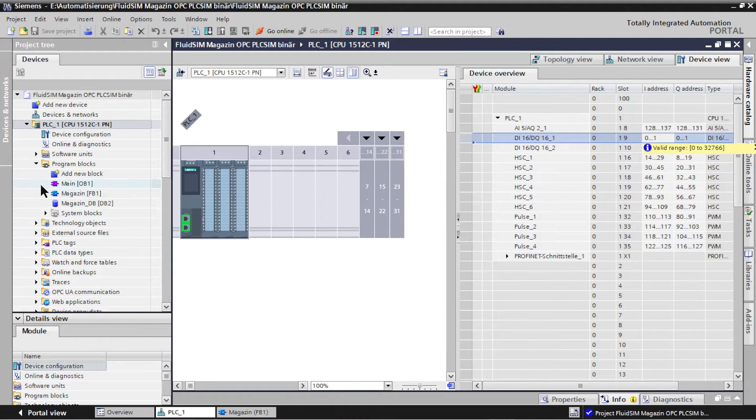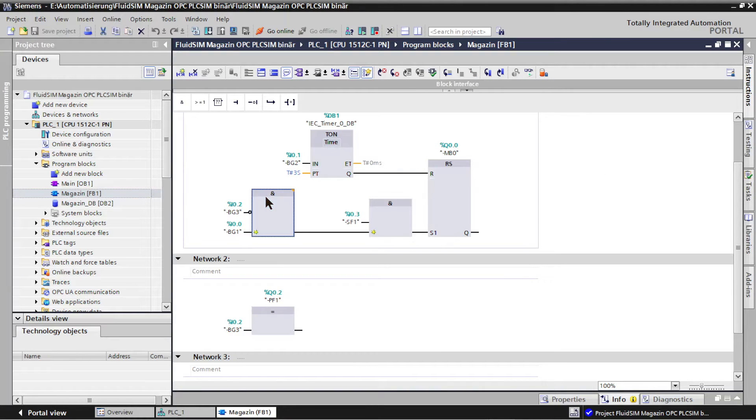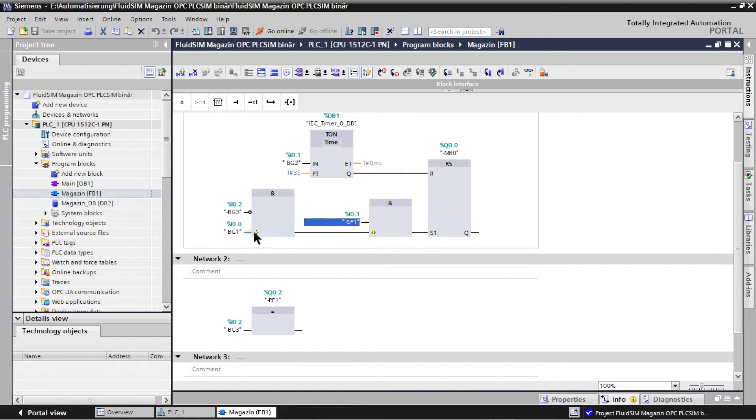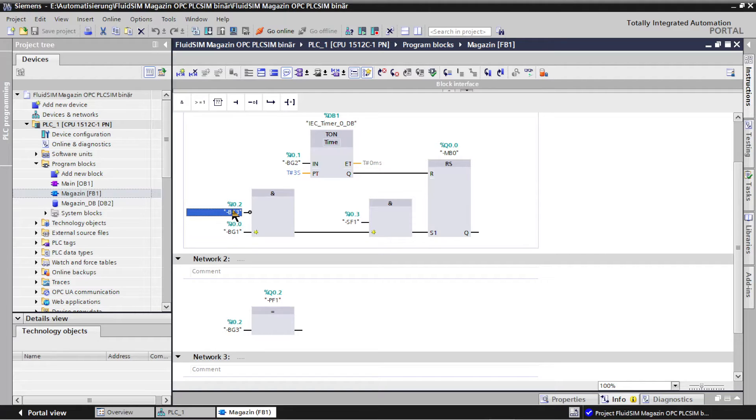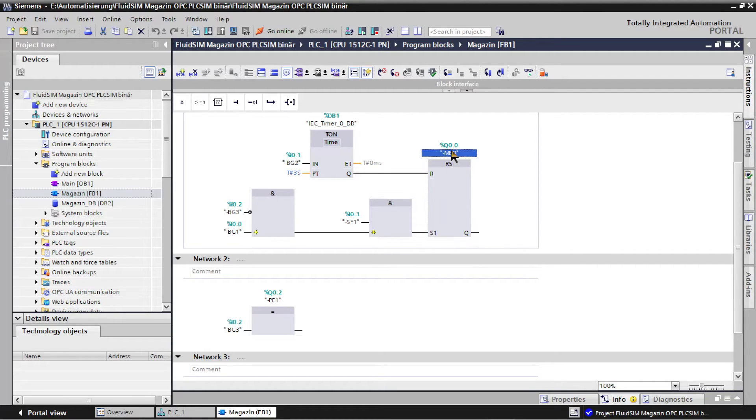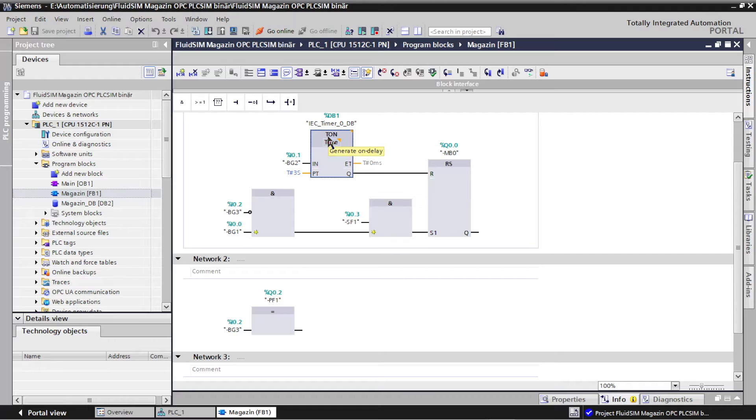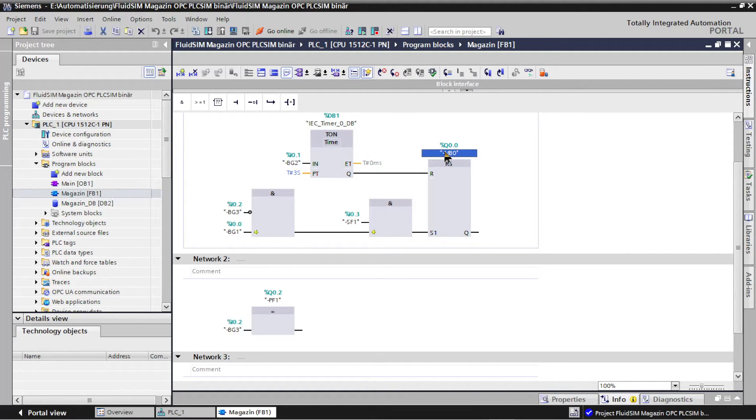Two AND blocks check the start condition by linking the signals of the start button SF1, the end position BG1 and the workpiece recognition BG3. If the start condition is met, an RS flip-flop is set and the output controls the solenoid valve. If the end position BG2 is reached, a switch on timer starts, which resets the flip-flop when it has expired. The drive MM1 retracts.